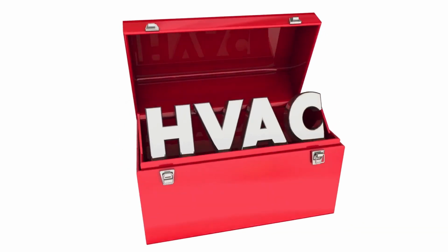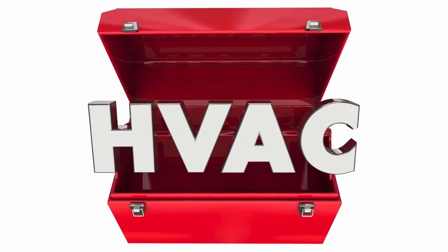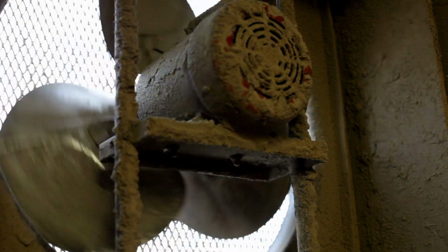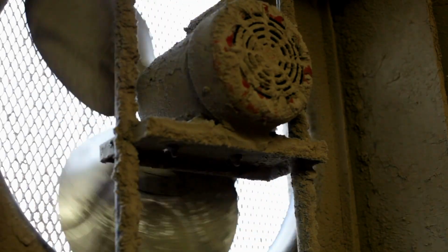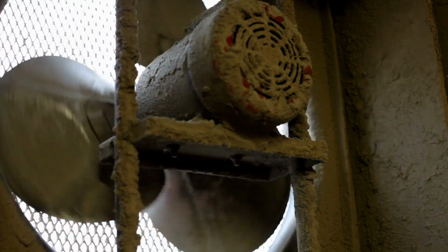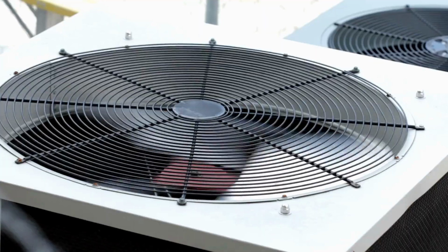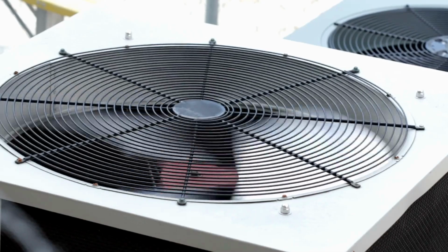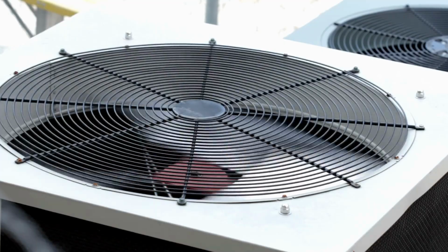Example is a fan and motor assembly. In large HVAC systems, a motor is often used to drive a fan through a coupler. If the two shafts are installed at a slight angle to each other rather than in a straight line, angular misalignment occurs. This can happen when the motor and fan are not aligned properly during installation, where one shaft might be tilted upwards or downwards relative to the other.